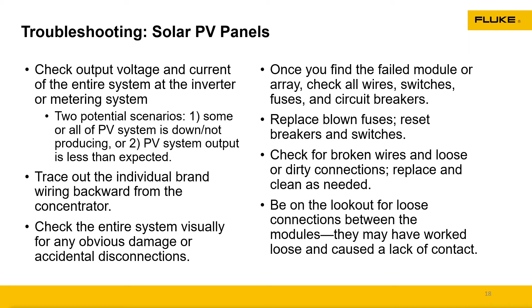But all of that is basically from the array, so that technician is going to be using some type of meter, some type of irradiance meter, and even a thermal imager to go out and check for all of that. They're checking for loose wiring. They're checking for any frayed or broken wires that need to get cleaned up, and then going back to the fuses. Now, again, as I mentioned, using a meter is going to be the key one.